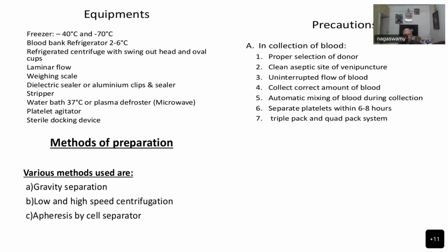Triple pack and quad pack systems are there, which can hold different components separately. Other precautions in centrifugation are balancing and use of rubber discs. The broad side of the bag faces the outside wall of the cup. The correct speed and time must be maintained, and look for any abnormal vibration.